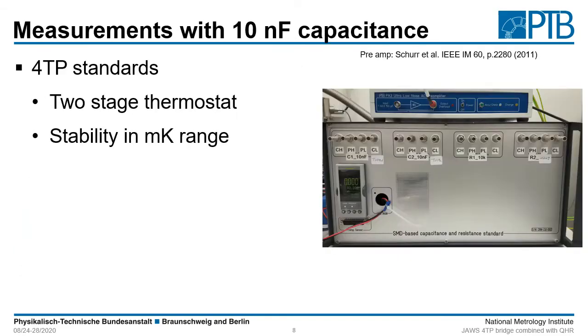Before coming to our first measurements I would like to show you our four terminal pair impedance standards. We have two 10 nF capacitors, one 10 kΩ resistor, and one 12.9 kΩ resistor. All of these standards are arranged in a two-stage thermostat which is stabilized to the millikelvin range.